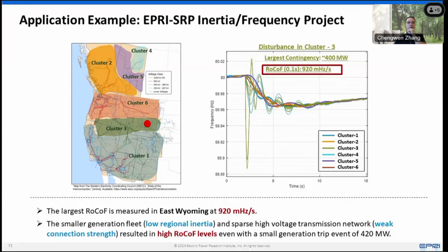However, this small event actually caused a very high rate of change of frequency in cluster 3. The highest we measured in this region is 920 millihertz per second. Many loss of mains protections, mainly in Europe, have a typical setting of 500 millihertz per second, although they can be relaxed nowadays as we have more and more IBRs. But 920 is a very high level of rate of change of frequency.